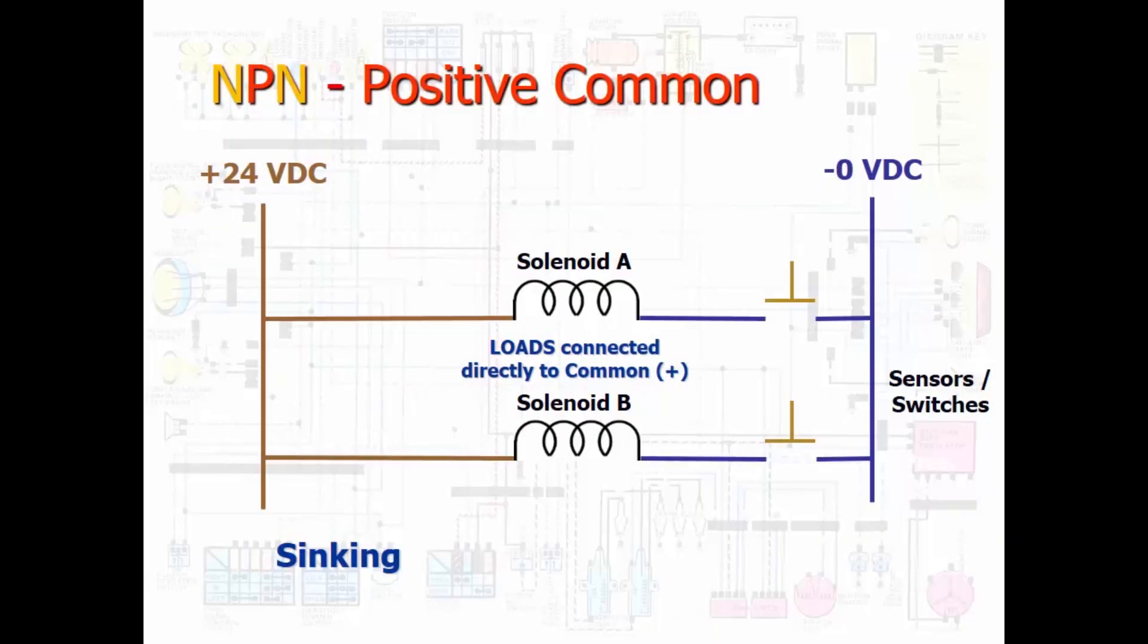However, if the circuit polarity should be NPN, the A and B solenoids are already connected to the 24 volt power. They just need controller signals to close the switches to sink to the negative common and thus turn A or B on.